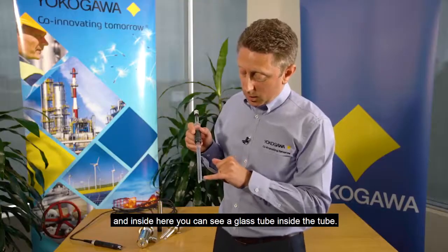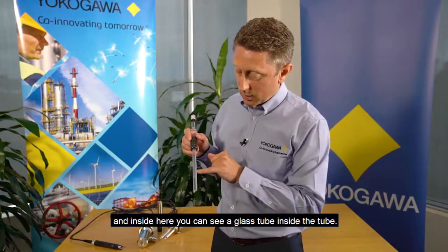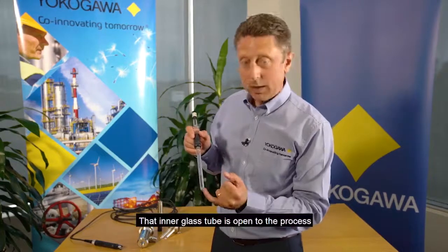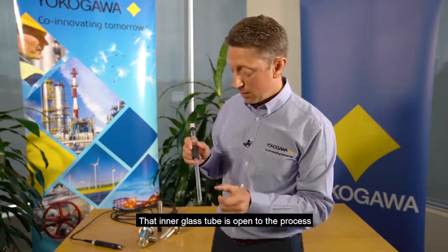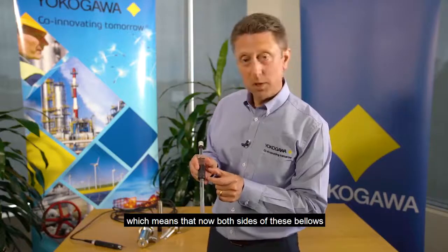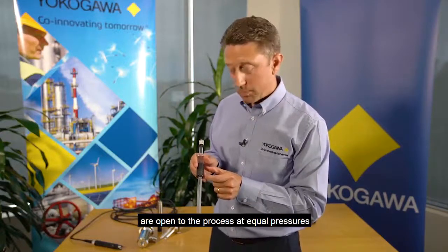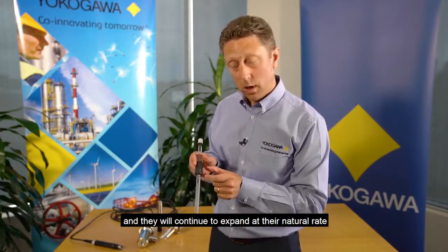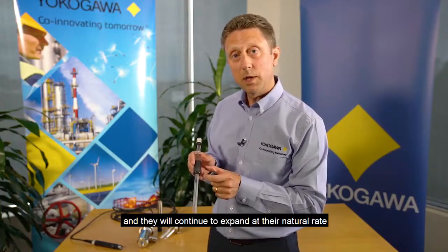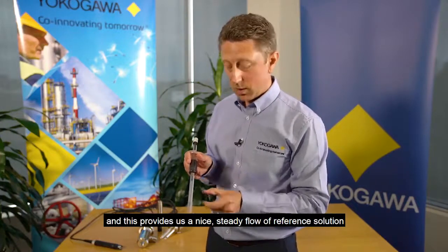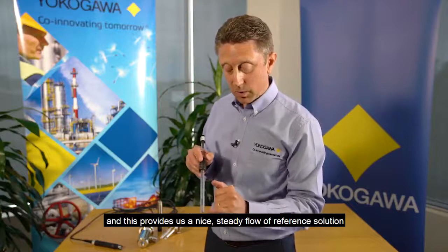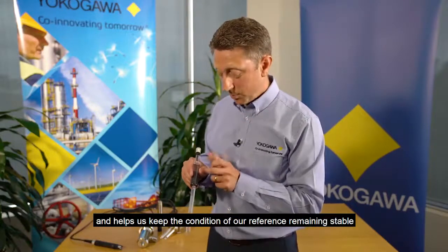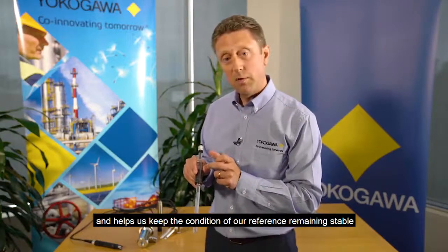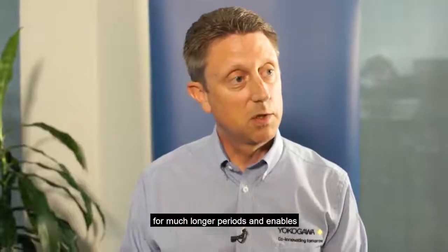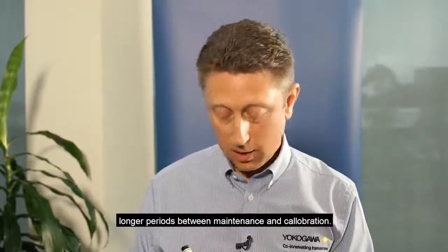Inside here you can see a glass tube inside the tube. That inner glass tube is open to the process, which means both sides of these bellows are now open to the process at equal pressures, and they will continue to expand at their natural rate. This provides a nice steady flow of reference solution and helps keep the condition of our reference stable for much longer periods, enabling longer periods between maintenance and calibration.